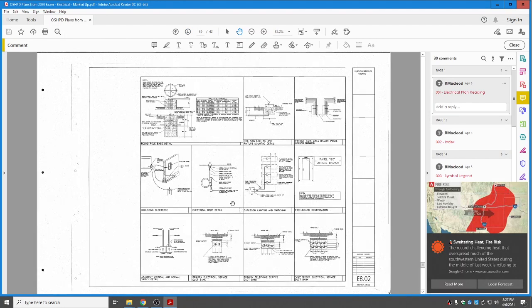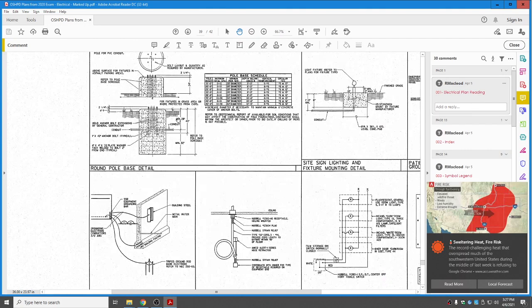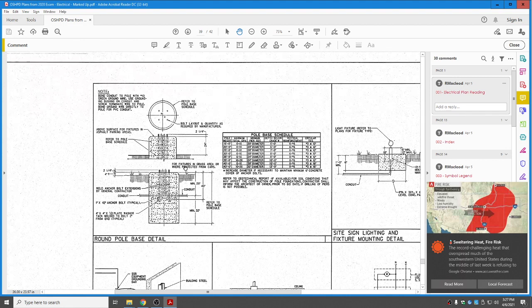Okay, on this page, top left, you have the round pole base detail for the lighting fixtures that are in the parking lot. Let's take a closer look. Okay, we have a note. We're going to bond the conduit to the pole with a number 10 green ground wire. We have a concrete base that's going to drop into the ground. There's some dimensions shown here and in the pole base schedule.